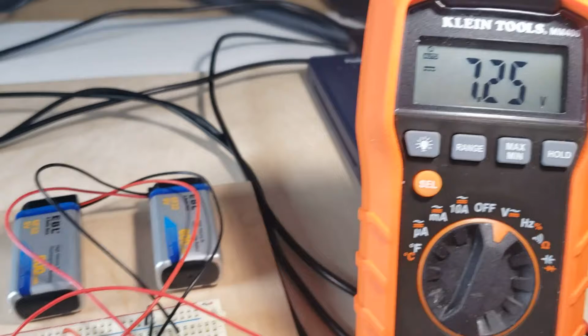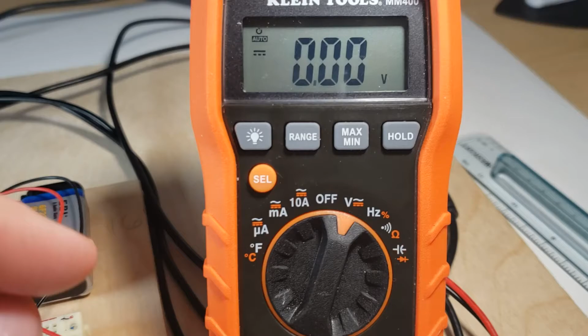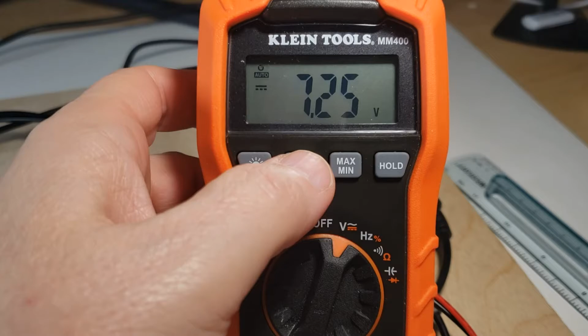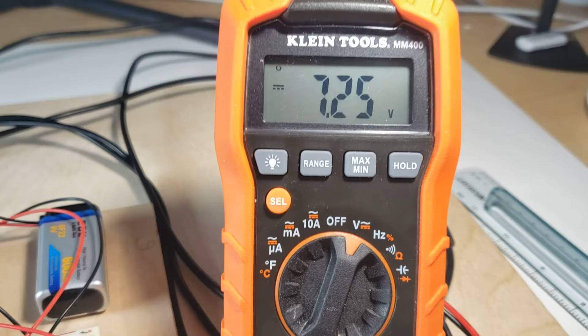Notice this icon tells me it's measuring DC. If you mistakenly have it set to AC, you'll measure 0 volts, so that's important to check. Right now it's in auto mode, and I normally prefer not to use auto mode because the measurements are quicker without it. So I'll take it out of auto mode, and it's reading 7.25 volts on the positive.